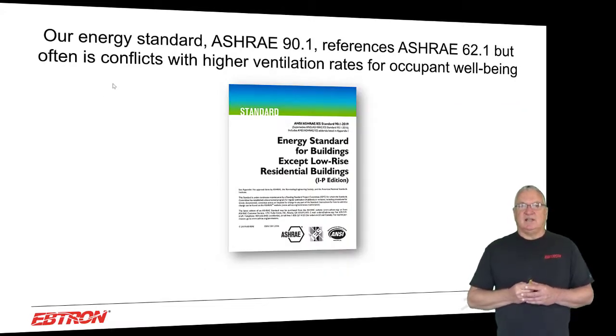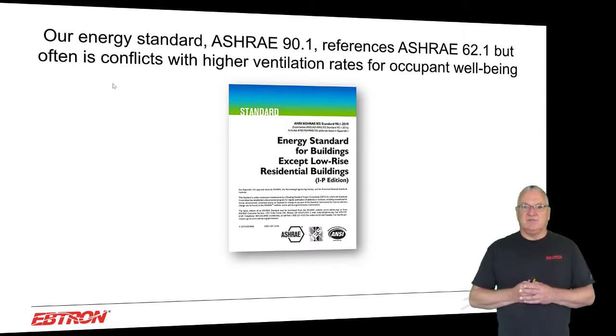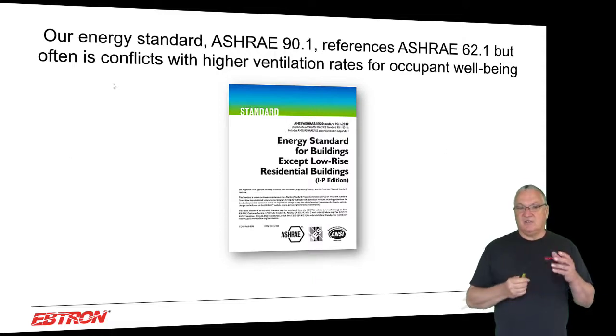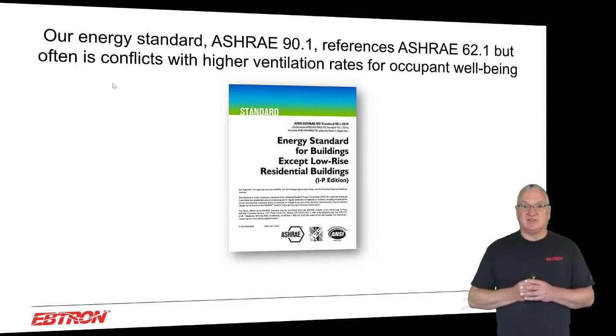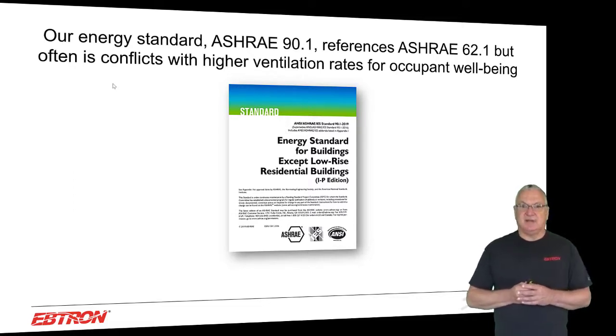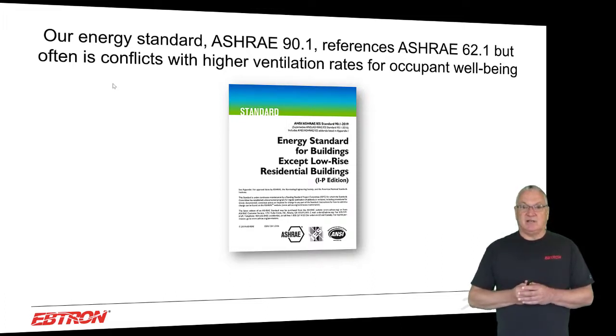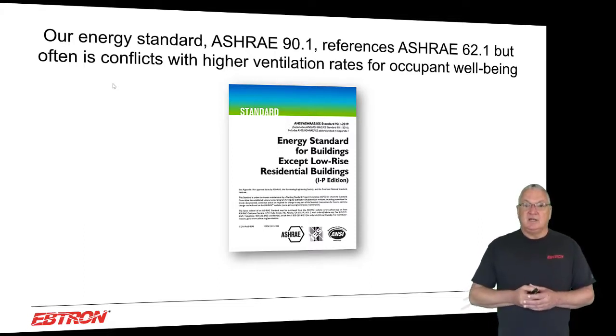There is a conflict here, because when you look at Standard 90.1 — which is really followed throughout the country and the world — one of the problems I have with 90.1 is it kind of goes against ventilation. Everything it's doing is trying to reduce ventilation rates and save energy. In my opinion, it's created some of the problems we have today, particularly as a result of its requirements for demand control ventilation. And there are public review documents out there now trying to even expand demand control ventilation, so we're going to have to be really cognizant about where this is going.